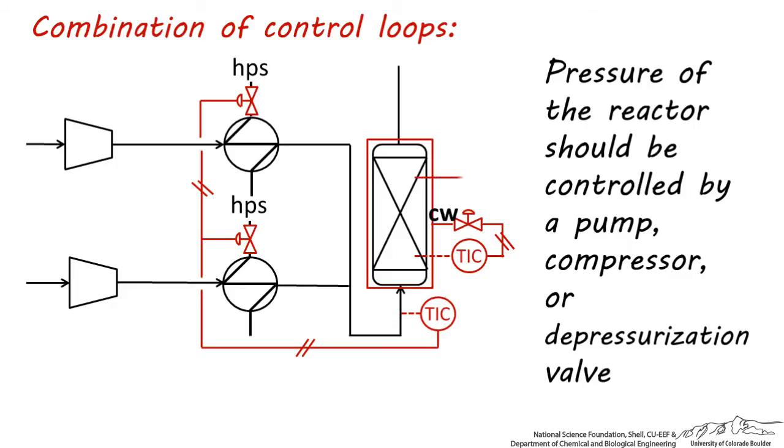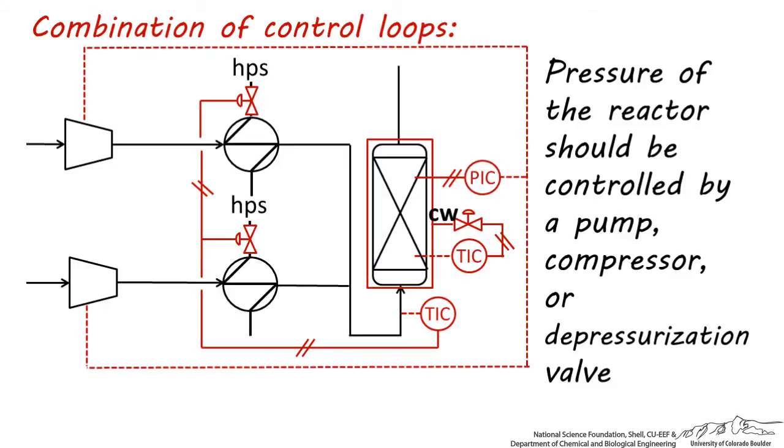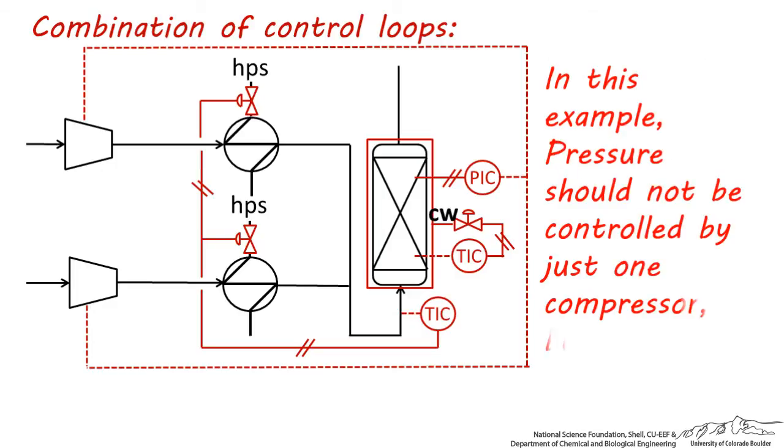It's a good idea to measure pressure inside the reactor, or even right before the reactor. Send that signal to a pressure indicator controller, which then will send an electrical signal to vary the power sent to each of these compressors. Depending on the power required for each of these compressors, power can be increased or decreased to evenly vary the pressure of the process stream. Just as with the heat exchangers, the pressure should not be controlled by just one compressor. This is because these pressures should be nearly equivalent when the streams are combined here before the reactor.